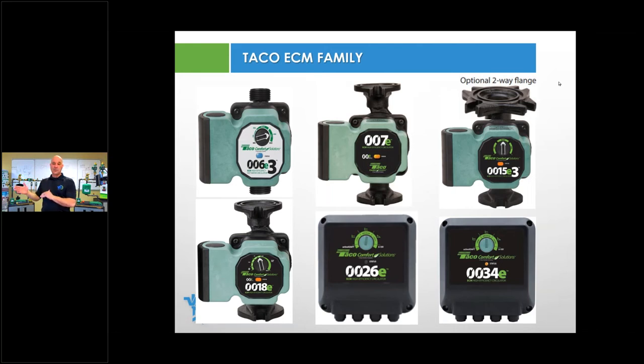Next step up would be the 0026E. This is a new launch for Taco. This will get us into that 200, 250,000 BTU range with an ECM circulator. And we have a bunch of different settings on there, depending on what type of system you're connecting it to. We go all the way up to the 0034E, which is right here. Again, this knob will give you a ton of opportunities to set the circulator up about four different ways.